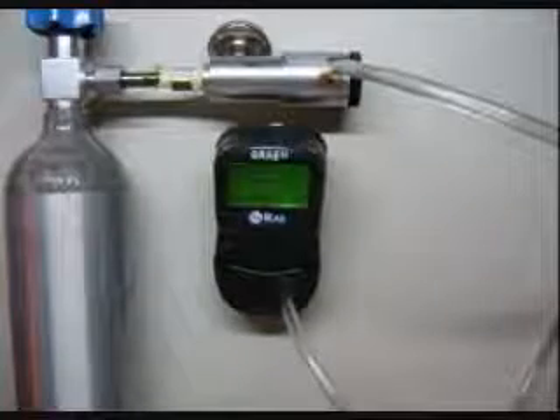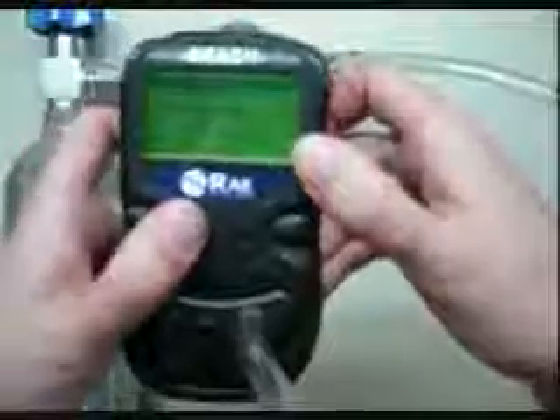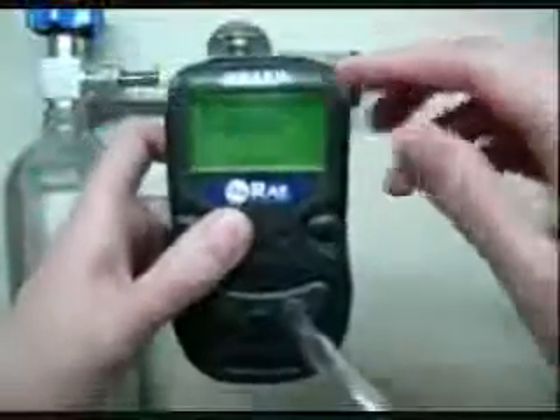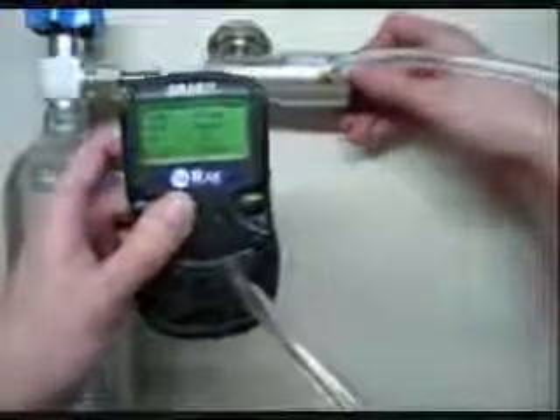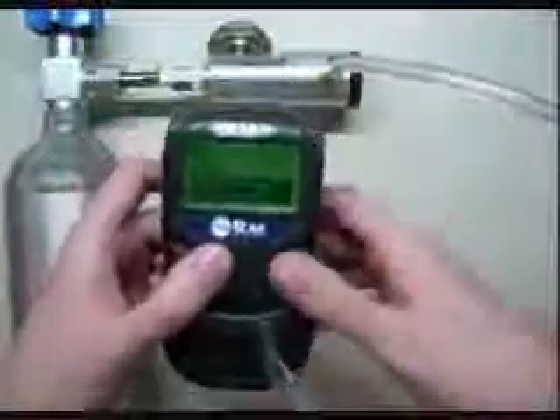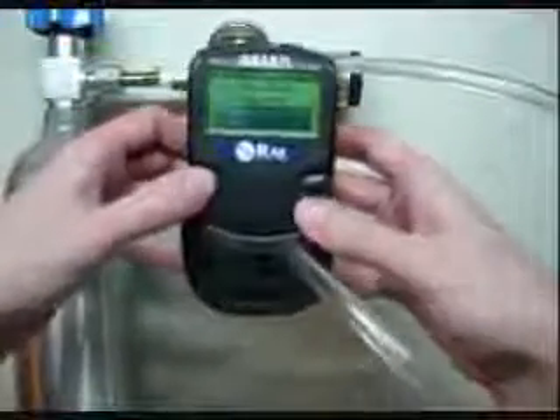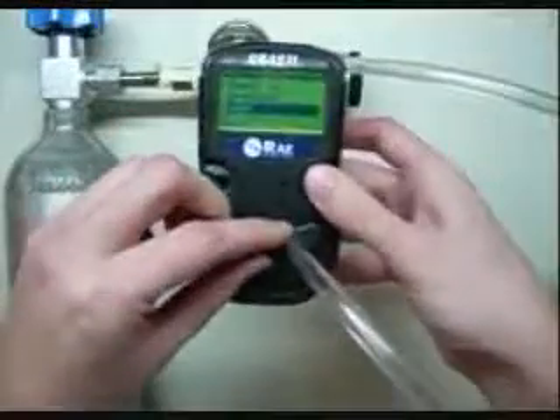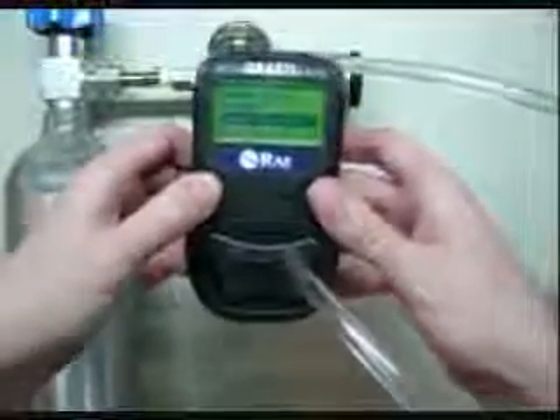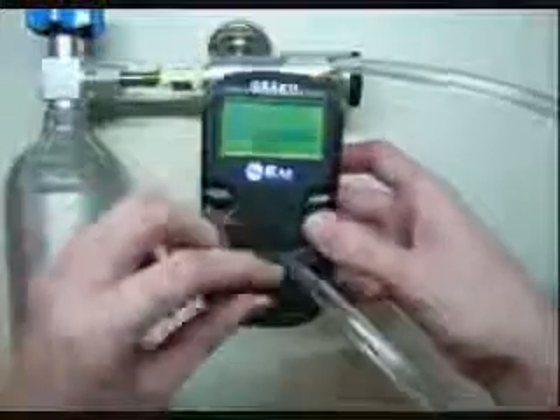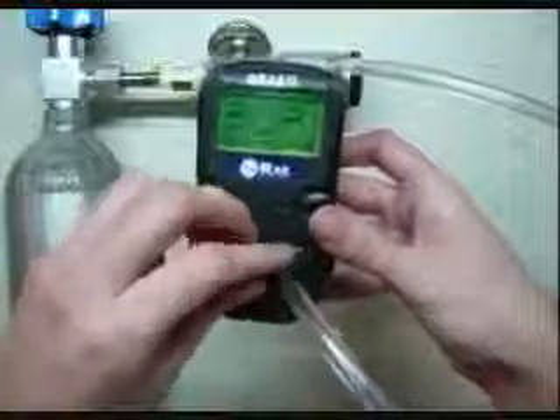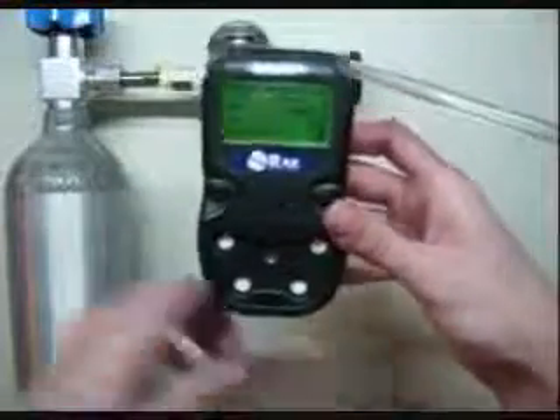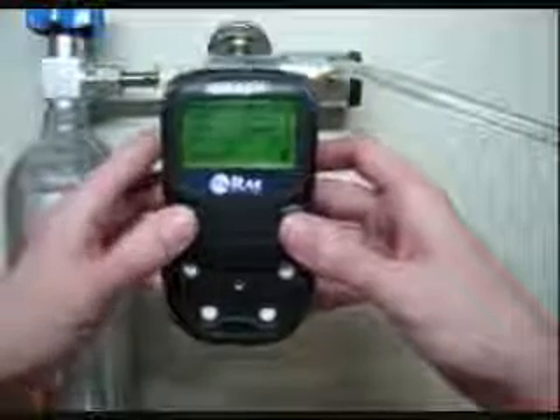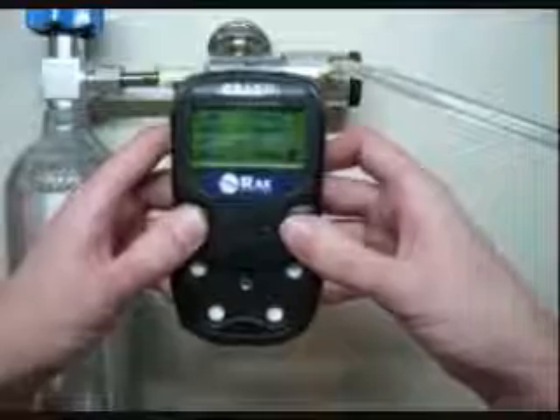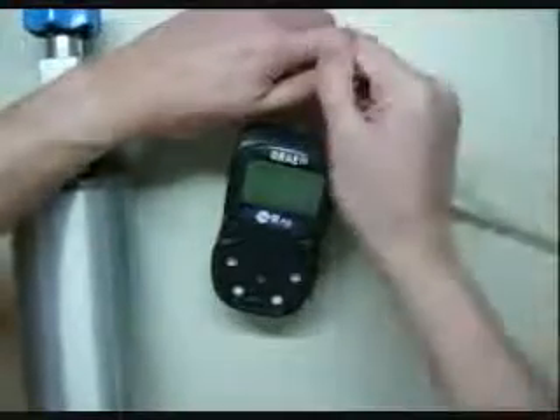Okay, now we're nearing completion. It's going to come up, say they're all calibrated, and show you the values it's gotten for each one. So you can go ahead and turn off your gas now. And it'll ask if you want to do a single sensor calibration. You're going to hit the button on the left to move down until you get to back. Do so again. Back. And it'll go into alarm here. So we're just going to unscrew the calibration cap. And we're just going to make sure it goes all the way back to 0. That's happening. Take the tubing off the regulator here.